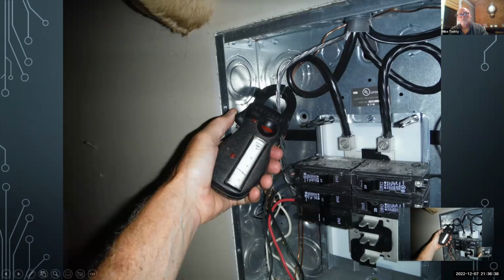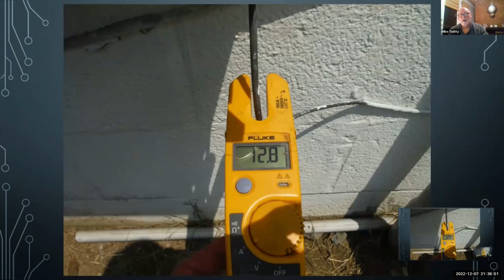So this metal enclosure, all these equipment grounds, this service, bare wire, and this SE cable, they're all energized, carrying current. Dangerous situation. This is a grounding electrode conductor at a commercial property that's got 12 amps on it. That's deadly. This one had a compromised neutral, and the neutral current was taking an alternate path, the best path it had, back to the transformer. This conductor went into a ground rod that was in a concrete slab full of rebar. The power pole with the transformer was at the corner of that same slab, all that rebar. So it had a good path back to the driven rod at that pole.